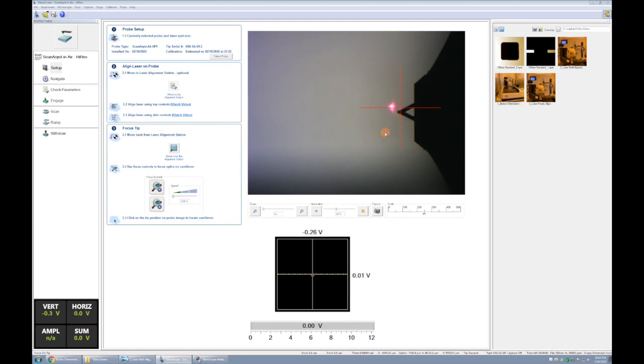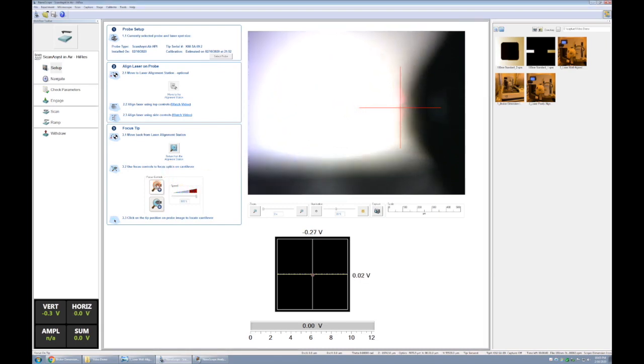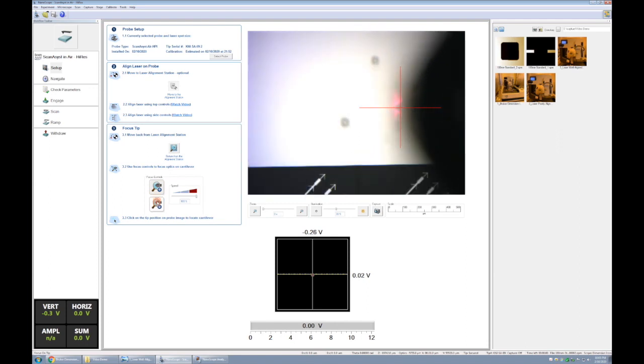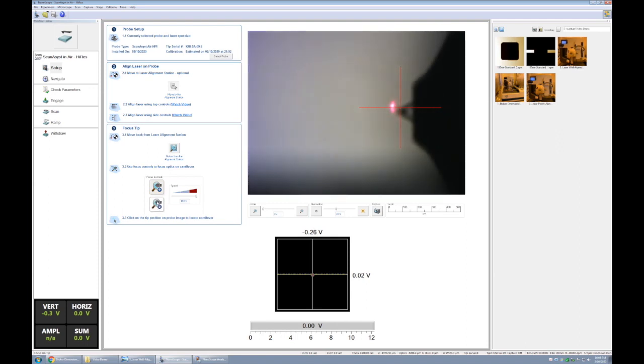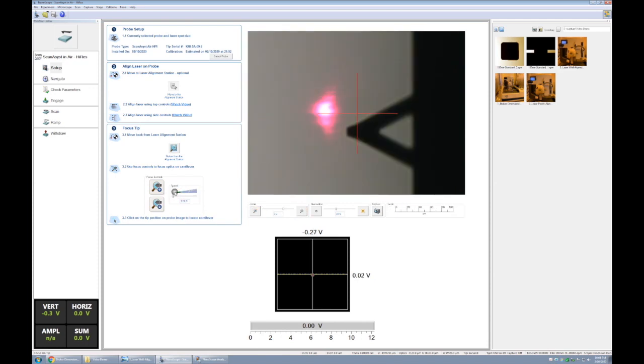And it's the silhouette image that ultimately allows us to visualize the laser and position it onto the cantilever, which we'll do very shortly. Now I'll just point out if you get to the alignment station and you don't see the silhouette image, you can always play with your focus controls. So for instance, I can go back up and go to the image where we were looking directly at the cantilever like we were before, and then you can play with those focus controls and go and find the silhouette. If it's out of focus, you can always digitally zoom in, lower the speed, and get a nice sharp focused image of the silhouette of the cantilever.